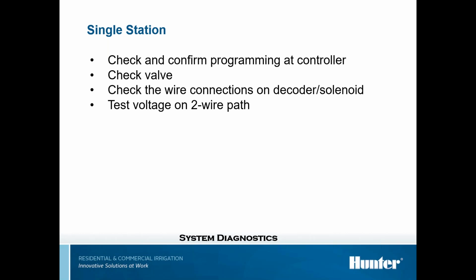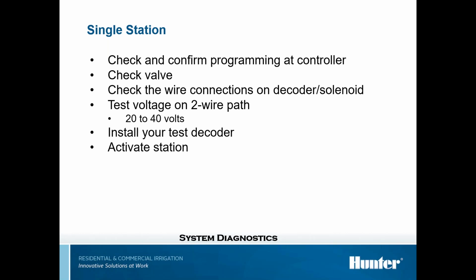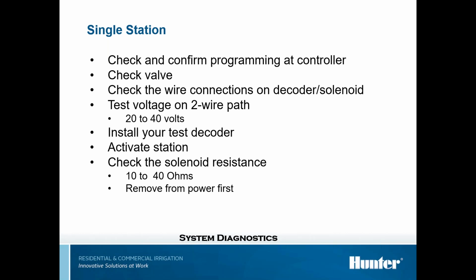Also, if everything still looks good, check your voltage on the 2-wire path. It's right here, it says 20 to 40 volts, but the sweet spot is typically 30 to 35 volts. 20 is getting kind of low. Look for 30 to 35 volts, somewhere in that range. If everything looks good and your decoder is still not reading, put your test decoder on and see if it will read that test decoder, and try to activate the station too. Check your solenoid resistance. Your solenoid that's on the valve currently should be between 10 and 40 ohms. When you read ohms on the solenoid, remove the power first. Don't read it with the power on. It's not a good thing, trust me.